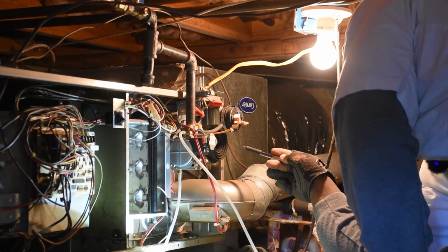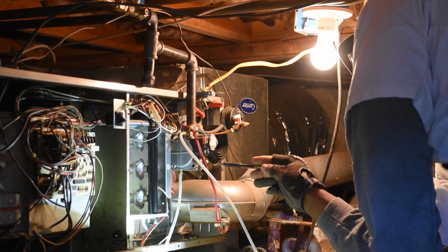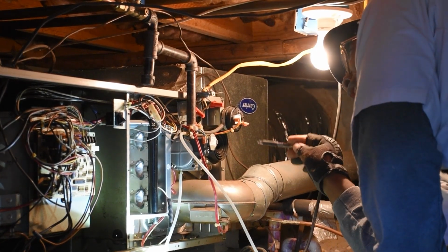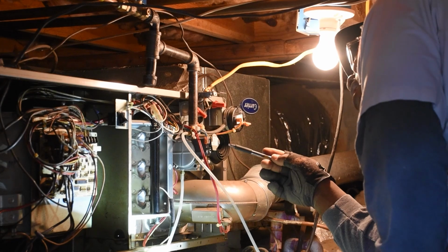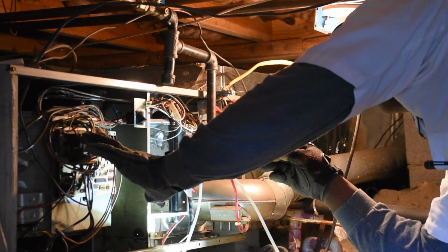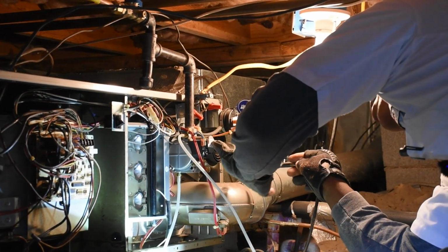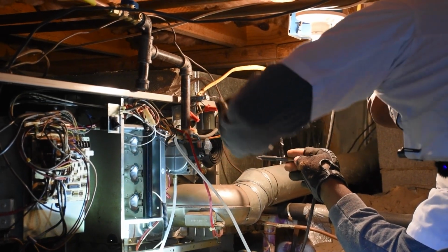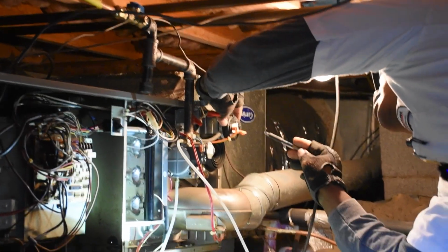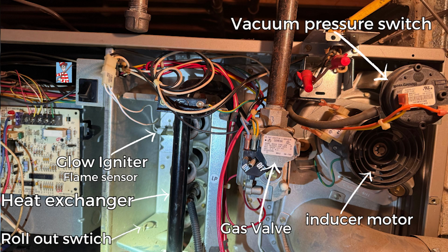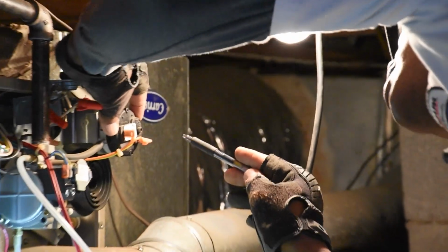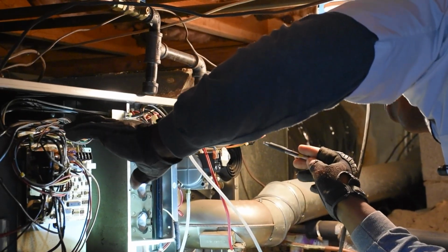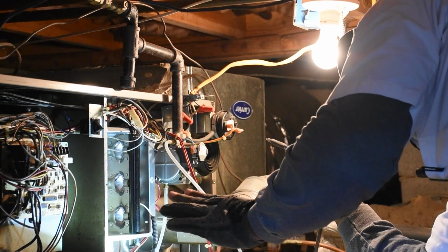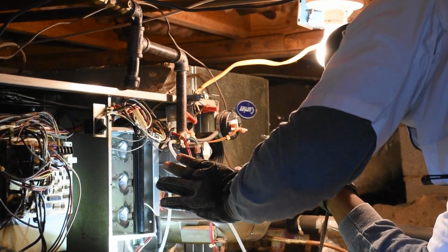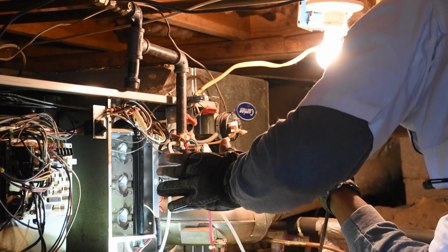What that does is it tells the system, okay, the exhaust flue is cleared and I'm okay to start the combustion process. The way it can tell the control board that is, once the inducer motor turns on, it creates a negative pressure and pulls in this device, which is called a vacuum pressure switch. Once it's pulled into a negative pressure, this switch gets closed. And once the switch is closed, the control board knows, okay, my flue pipe is cleared, I'm not blocked. So I'm okay to start the process of creating the combustion, the flame inside.